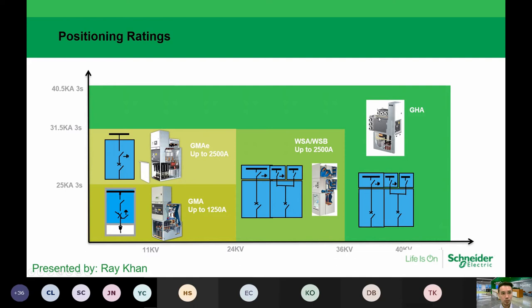Even as you go into the GHA, you can see the number of busbars here, with an option where we can go for a double busbar. All right, the double busbar options are commonly called for, especially in critical applications like data centers or hospitals. In data centers, a lot of the time the amperage can go up to 2500 amp, so a double busbar will be a good choice in here. That can actually give a certain redundancy in terms of the power design.